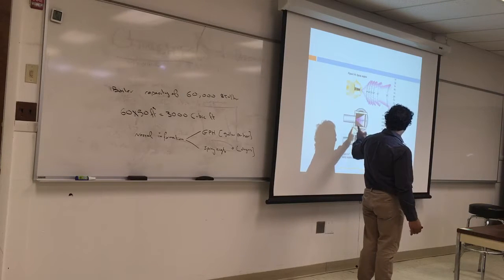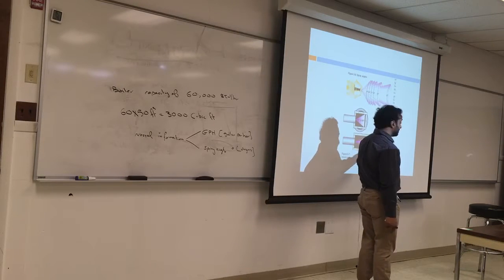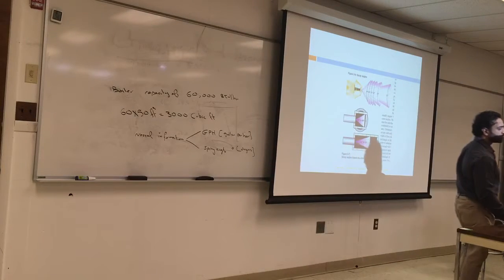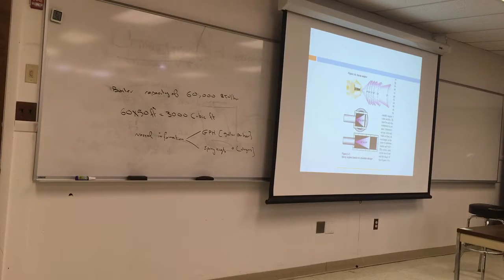So there is some specification. This is from the book for the angle, and that is where you actually want the flame. For longer chambers, you'll probably have less angle, and the spray will go further. You can't see inside the chamber to tell if it's touching. If it's smoking, then it's because of that. You cannot see the flame, so you want to adhere to the instructions. If you get a lot of smoke, you might want to check, change the nozzle and see what you get.